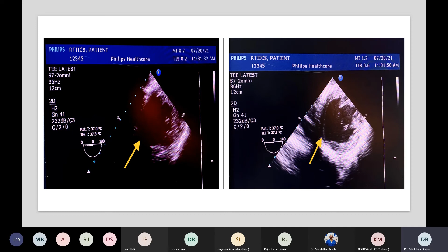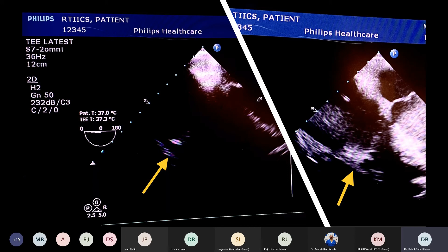And this is something called time gain compensation. Again, it is a 4-chamber, but I cannot see the lateral tricuspid annulus well. What was happening was, my sound wave is not coming with the proper energy and intensity to that particular depth. So there is a button called time gain compensation, and as I increase it, the intensity at that particular depth will be increased. And now, after changing the time gain compensation, you can see that the lateral annulus of the tricuspid valve is clearly seen, so that you can do a TAPSE, you can do those additional things you can be doing.